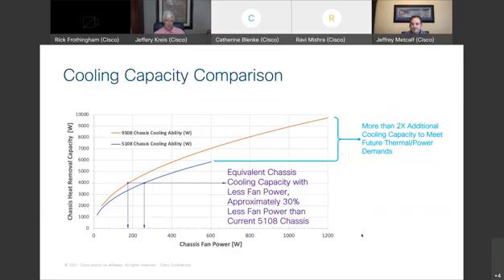Okay, next slide. Okay, so this is another example, just a different way of looking at it. You have the orange curve, which is the cooling capacity of the X-Series chassis. The blue curve is the cooling capacity of the existing 5108. On the horizontal axis is chassis fan power, the amount of power that the system fans are drawing. And on the vertical axis, you have how much power is being removed from the system. So every watt of electrical power that goes into the chassis, or any server for that matter, is removed as heat energy. So if the solution was consuming 4,000 watts, or 4 kilowatts, you draw a horizontal line to see where the intercept will be on that curve.